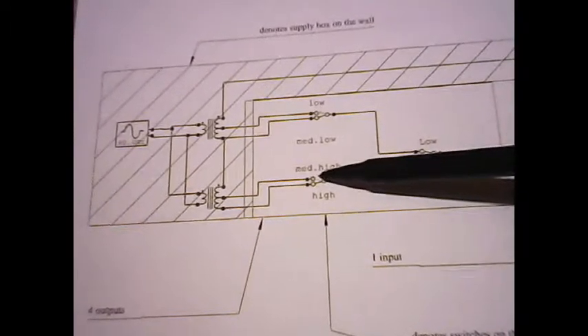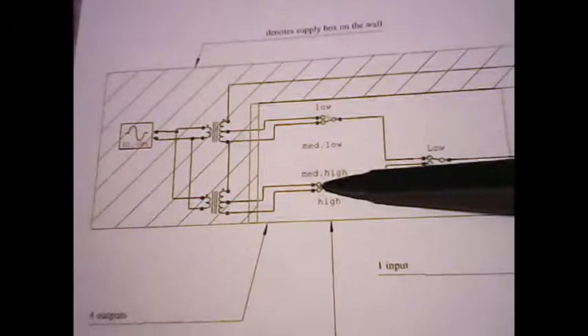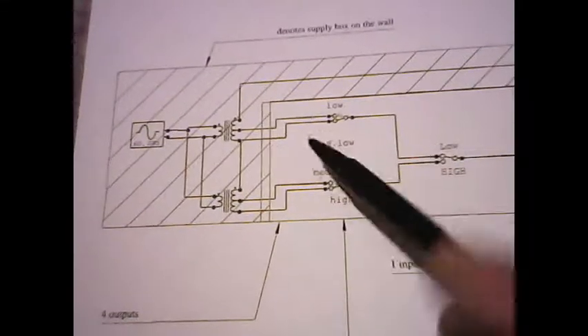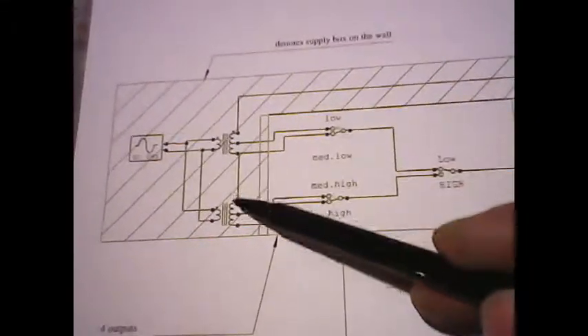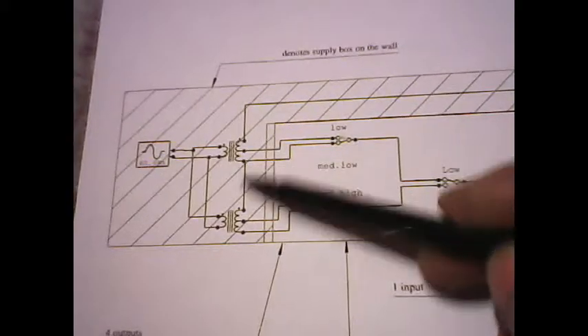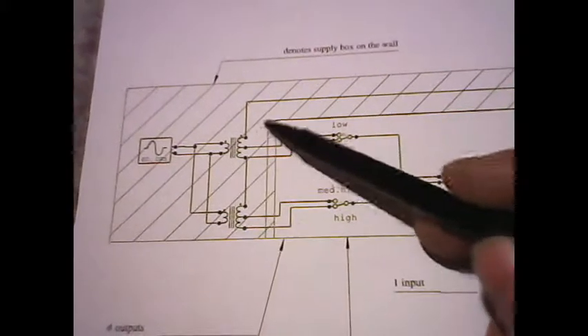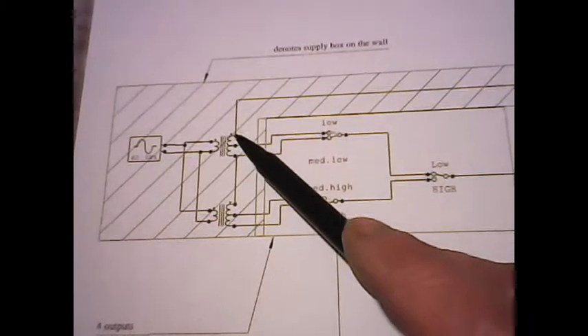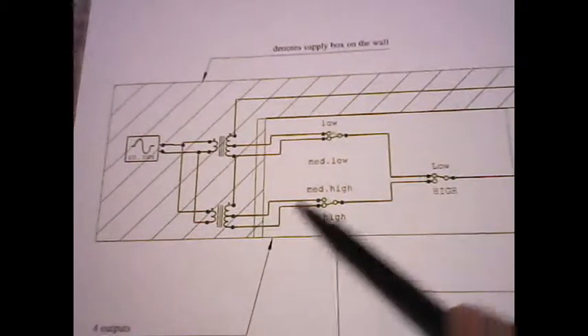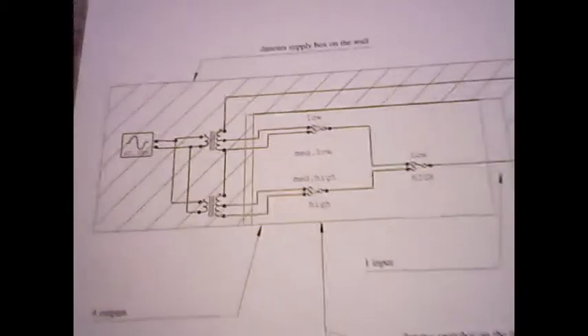If this switch is down in the high position now, that means this transformer plus this transformer, getting close to 80 volts -- 40 volts here and 40 volts here -- will both be in the circuit to give me full power and full speed output.